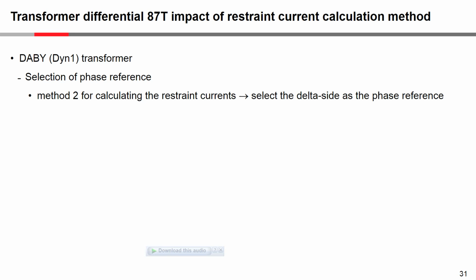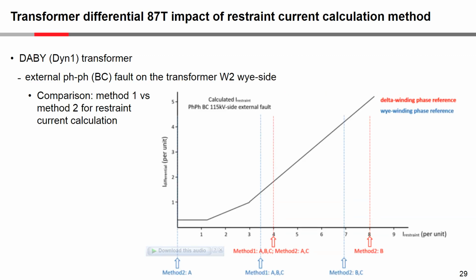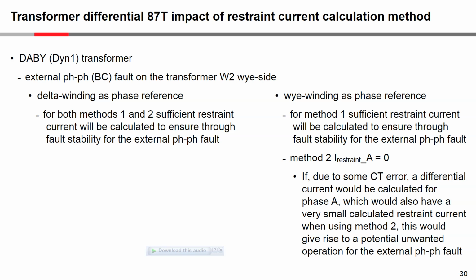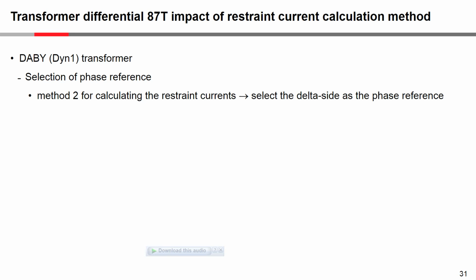If we are using method 2 for calculating the restraint currents, then we really need to select the delta side as the phase reference, because if we choose the Y side as the phase reference, we could potentially have a problem. So method 2 for calculating the restraint currents really means we should select the delta side as the phase reference.